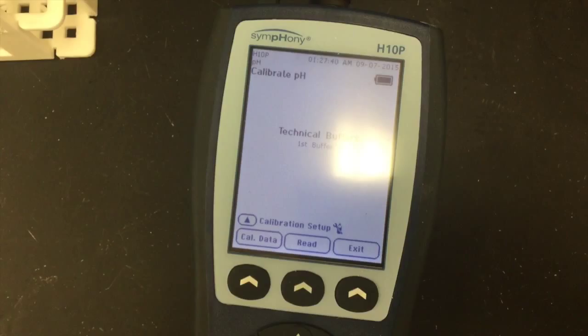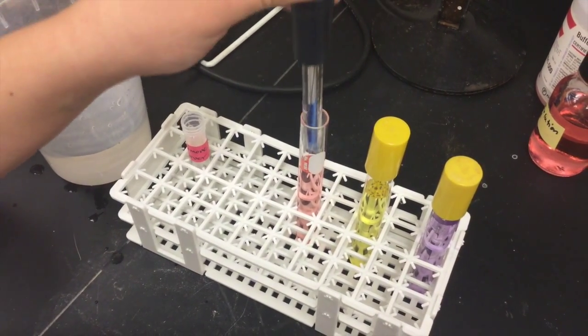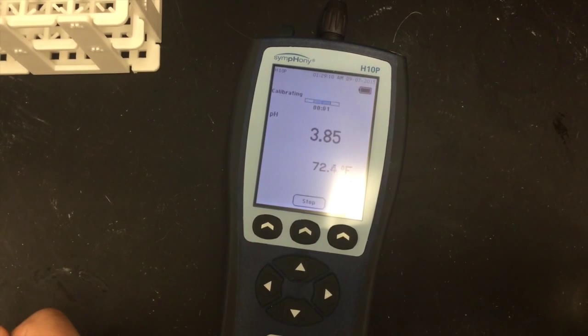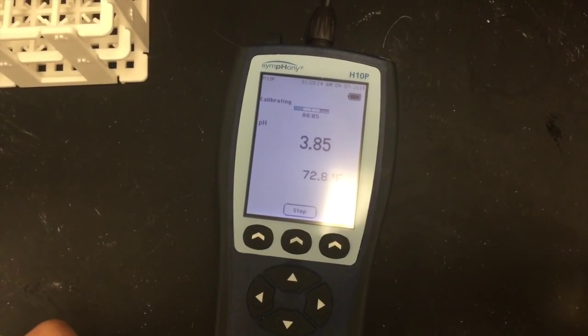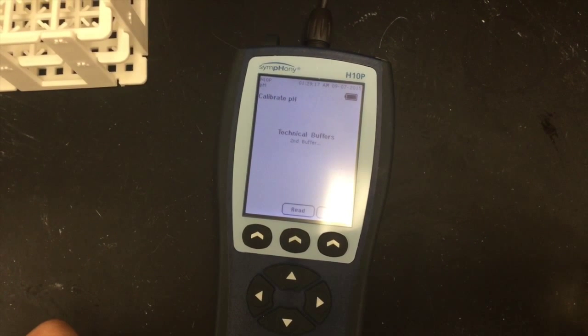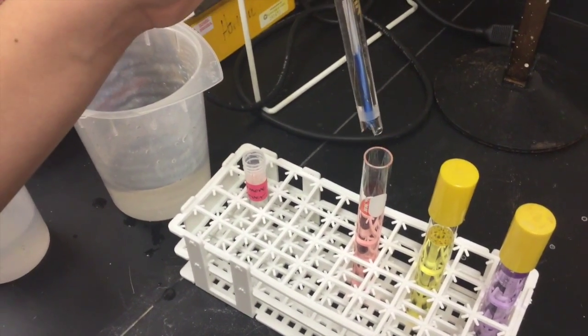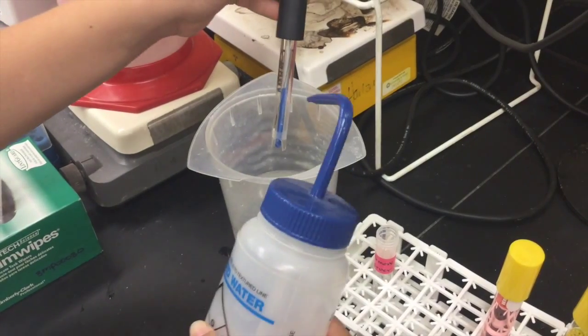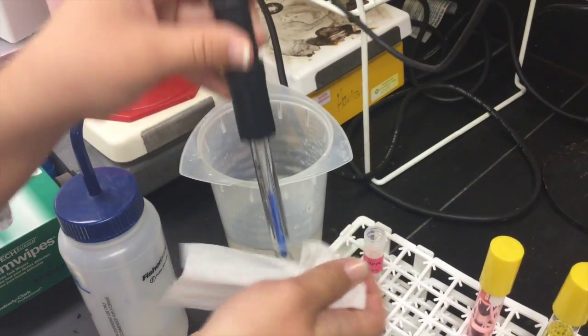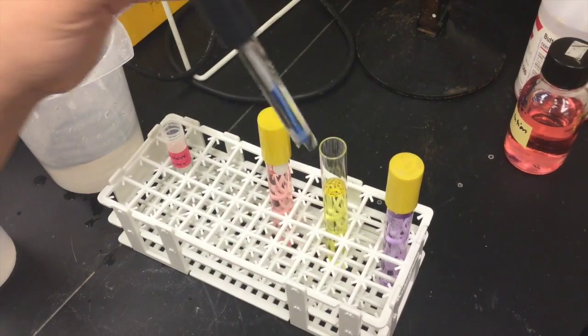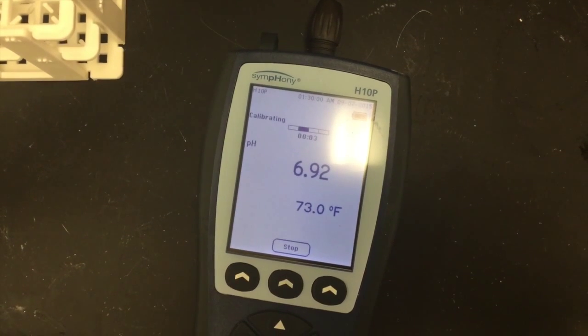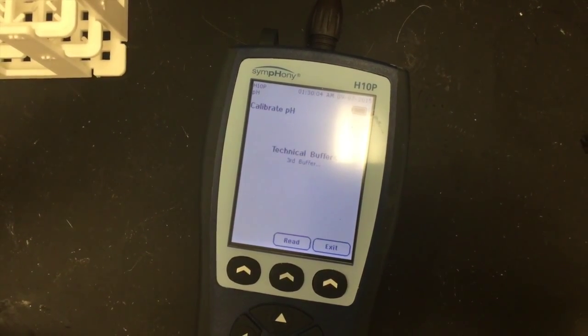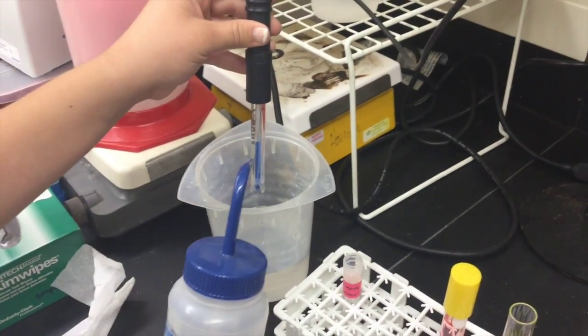The pH meter is pre-programmed to calibrate using buffers of pH 4, 7, and 10, so you must test the buffers in that order only. Uncap the test tube filled with the buffer of pH 4 and insert the probe. Then press Read. It will take a few moments for the meter to calibrate, at which point it will be ready for the second calibration buffer. Remove the probe from the first buffer and rinse it off again. Then place it into the second buffer. Press Read again and wait another few seconds. Repeat the same procedure for the third calibration buffer.